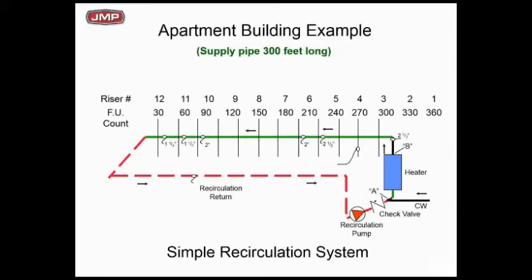We go to the fixture unit charts and come up with the GPM to size the pipe. The pipe has already been sized: 2½ inch in the first section, stepping down through each section all the way to 1¼ inch at the very end. Then the red piece of pipe is the hot water recirculation return line — we draw water through that back to the water heater to offset the heat loss in the 300-foot supply pipe. In our example, we're going to hold it to a 10-degree delta T, coming up with the heat loss in BTUs per hour and the GPM required, to keep hot water available at riser number 12 even at 2 a.m.